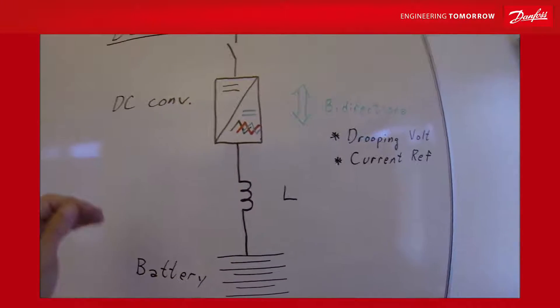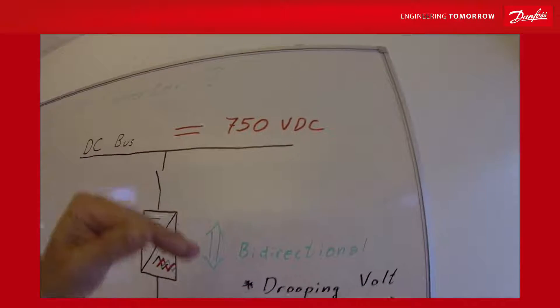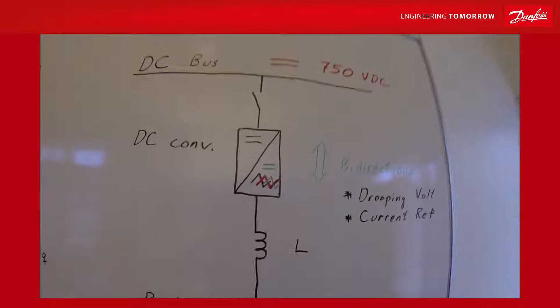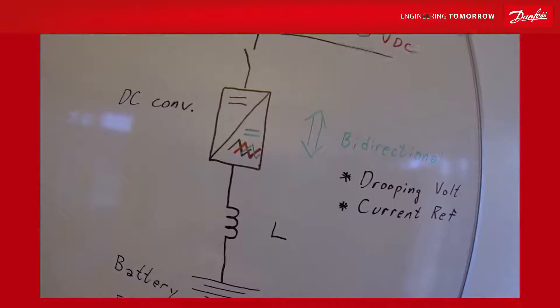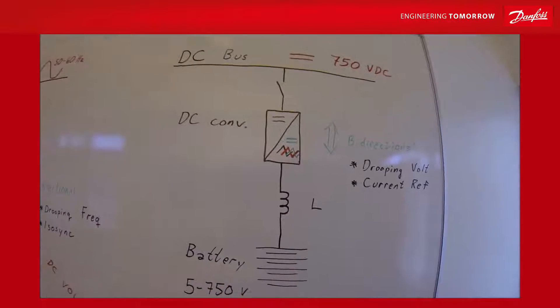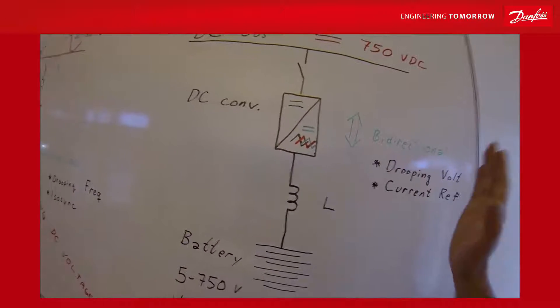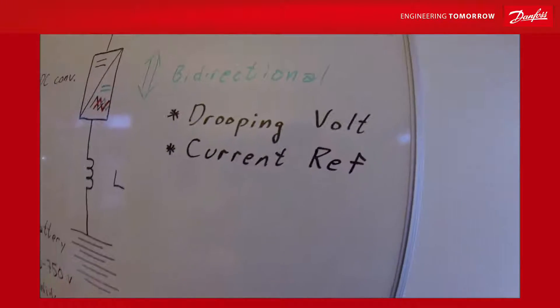That means when the current is bigger then you reduce the voltage a little bit and then it will take off the load. So you adjust the drooping to be the same as other energy producers on the grid and then you will have the same drooping profile. It's just like paralleling active front end. So drooping is an easy way of sharing the load with other producers.